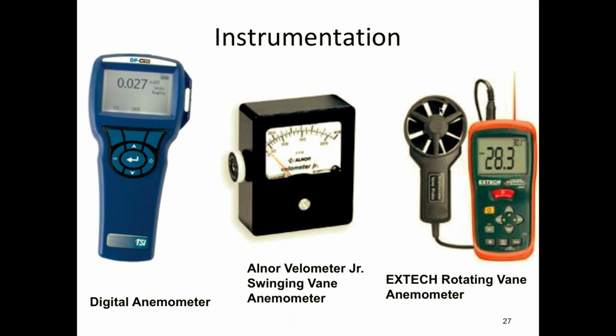Right now it's set on units of feet per minute. In the United States, everything we do in ventilation is usually in feet, cubic feet, and minutes in terms of volume and pressures. In most ventilation systems, instead of PSI or other pressure measurements, you're usually talking about inches of water. Imagine this: instead of a pressure in pounds per square inch, you talk about how many inches of water that pressure will hold up in a column. That's why we call it inches of water.